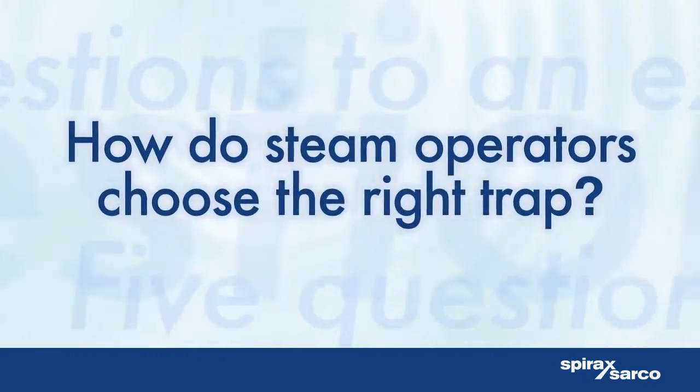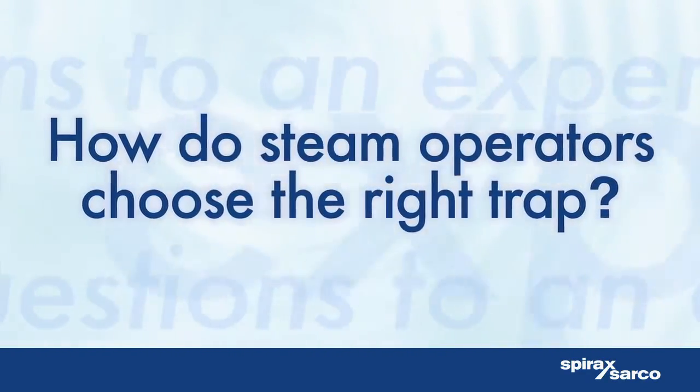How do steam operators choose the right trap? Picking the right steam trap for the job is not always straightforward and it really is worth seeking advice. It depends on the application. If there is a lot of starting and stopping then a thermostatic steam trap would be the good choice. On the other hand, an application with varying loads is best served with a mechanical trap because it responds quickly to changing loads.